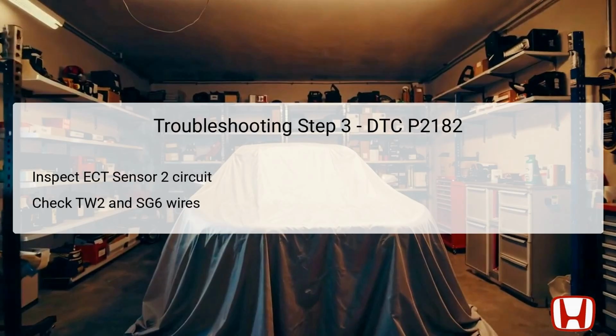It is crucial to check for unintentional disconnections, wear, or corrosion along these wires, as such issues can lead to inaccurate signal transmission to the PCM. A successful inspection will reveal continuity with normal resistance levels, indicating there are no short circuits or open wires affecting the sensor's function. Should any abnormalities arise during this inspection, repairs to the circuit will be necessary to resolve the DTC.